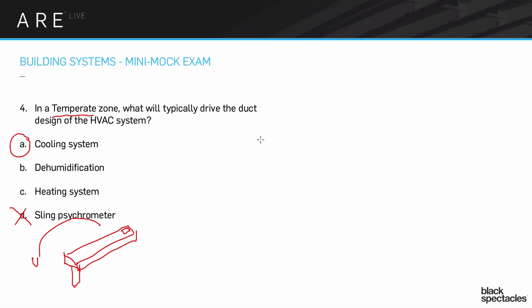And the reason for that is if you think about how hot the air is coming out of an air handling unit in the heating season and compare that to the air of the room, let's say we have air coming out at 110 degrees and the heat of the room is say 68. So we have a temperature difference of about 42 degrees. This is in the heating system in the winter.